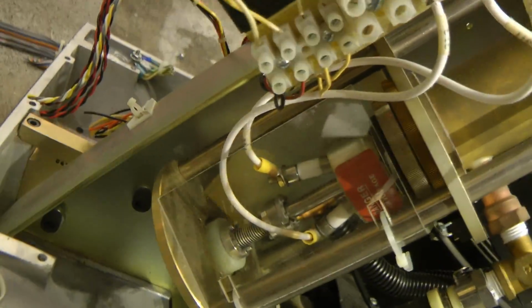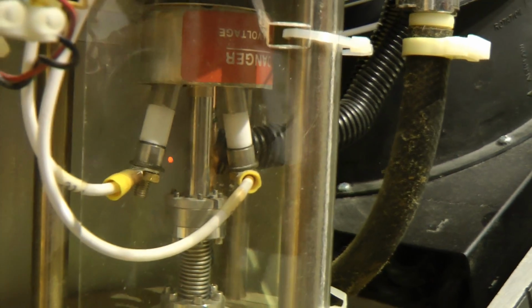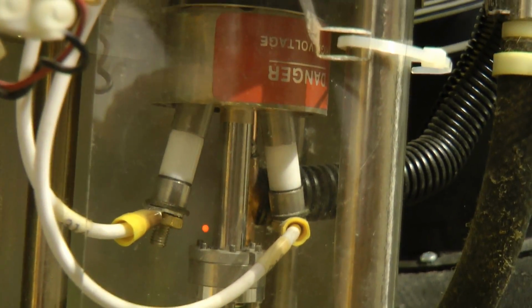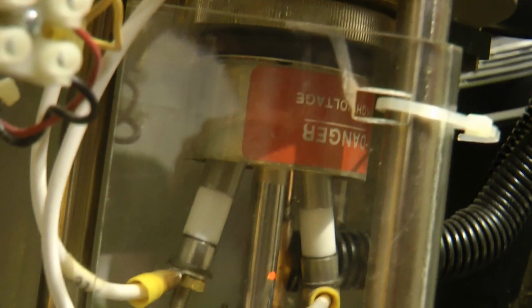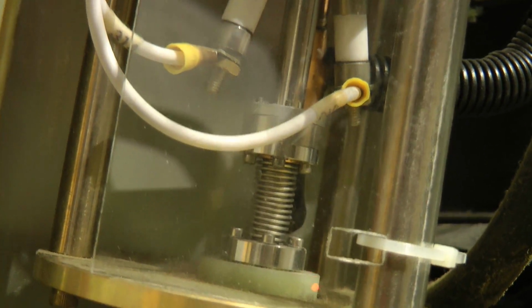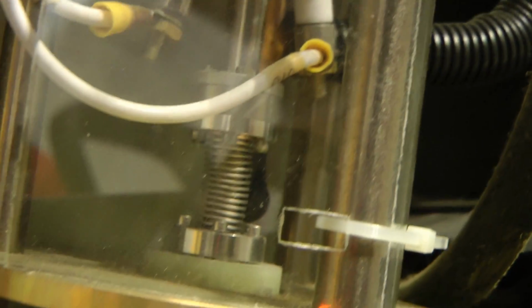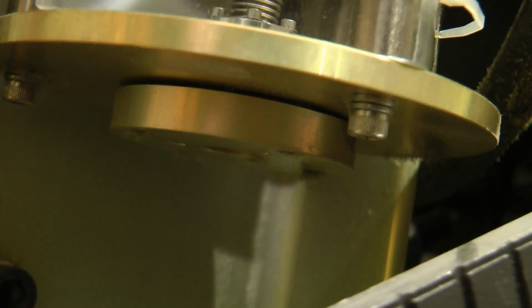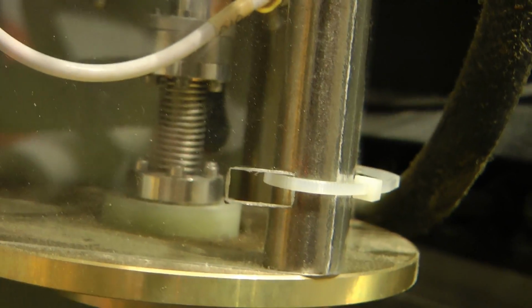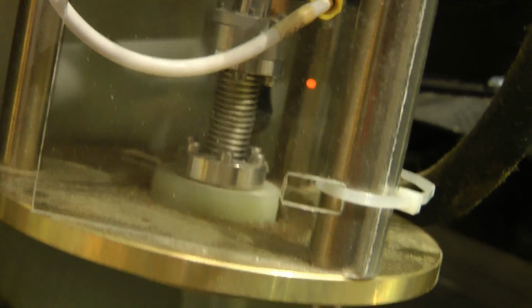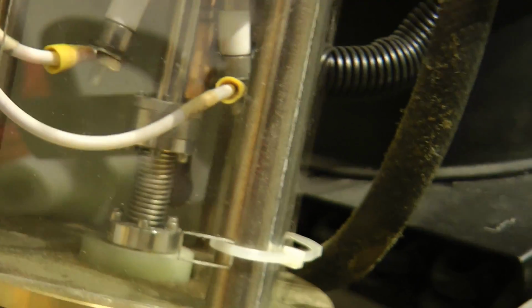Here is the actual filament connections into the tube. See the nice insulators there. I think that's where the laser beam goes down, across this little bellows. And on the bottom here, I think, is the adjustable high reflectance mirror, and you can probably trim the angle of that to get the beam going straight down the resonator cavity.